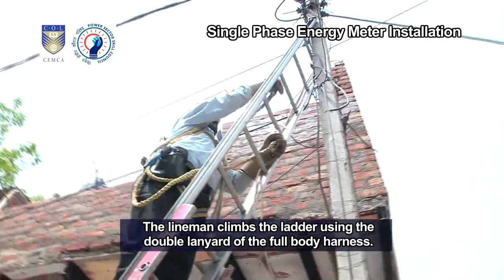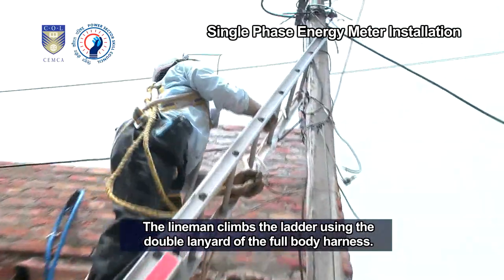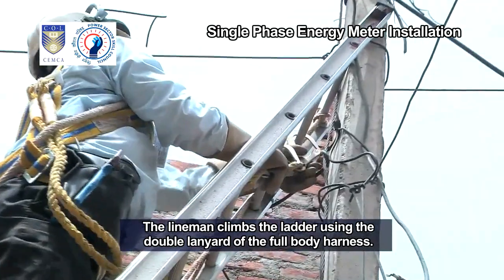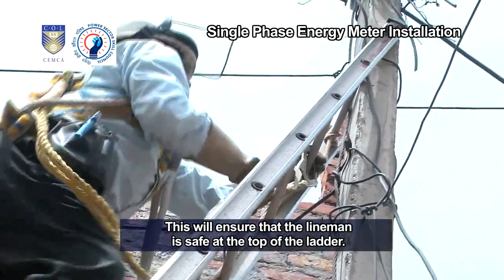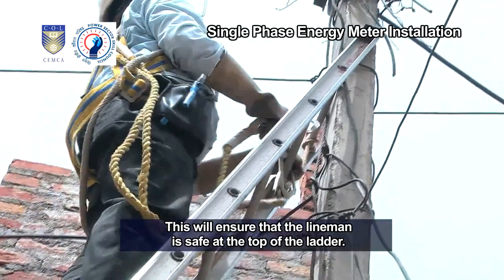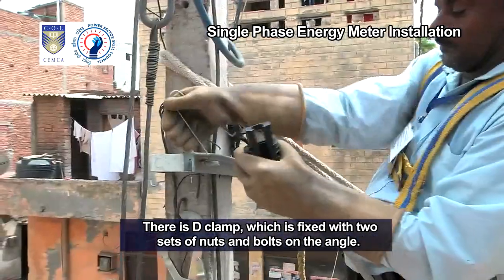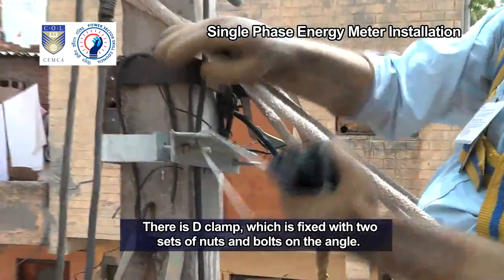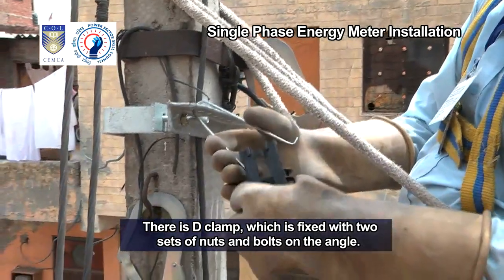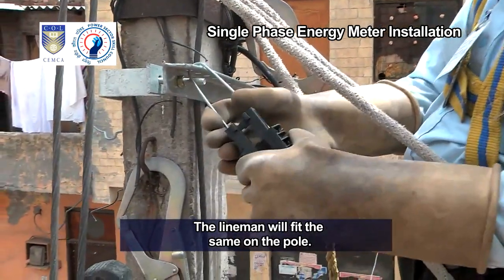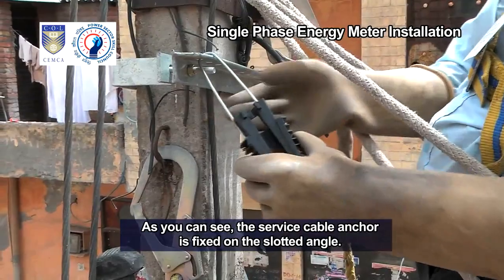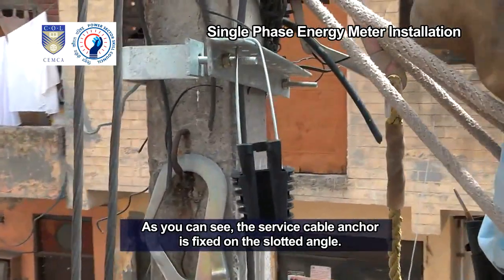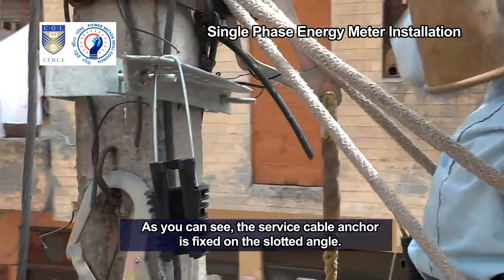The lineman climbs the ladder using the double lanyard of the full body harness. This will ensure that the lineman is safe at the top of the ladder. There is a D-clamp, which is fixed with two sets of nuts and bolts on the angle. The lineman will fit the same on the pole. As you can see, the service cable anchor is fixed on the slotted angle.